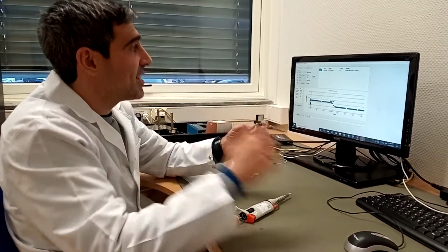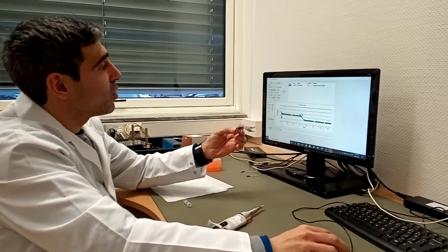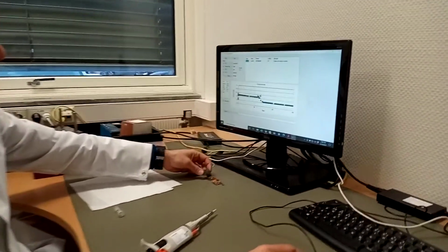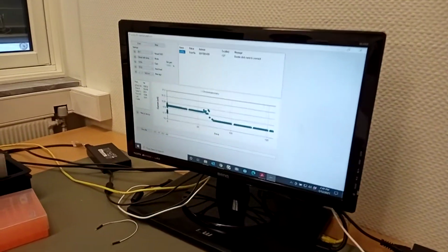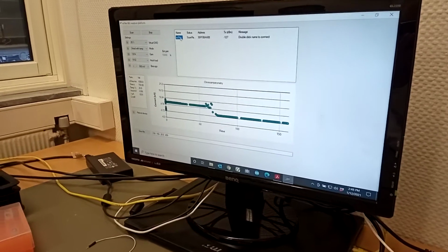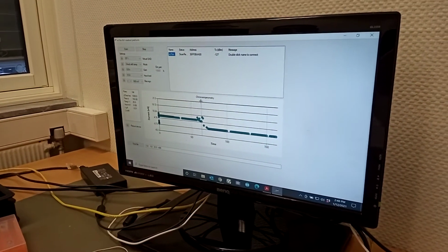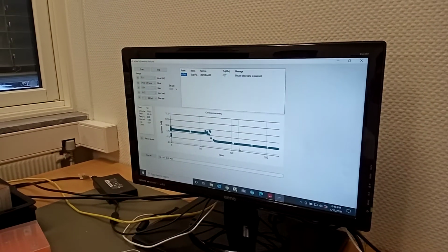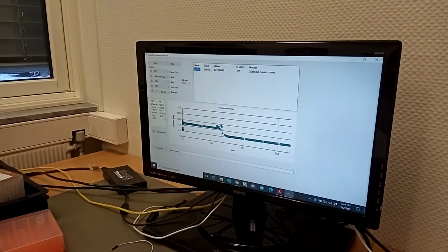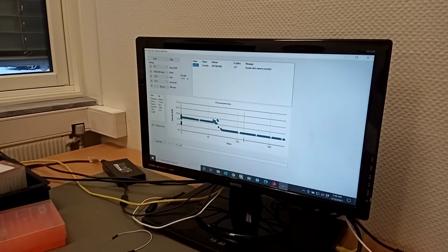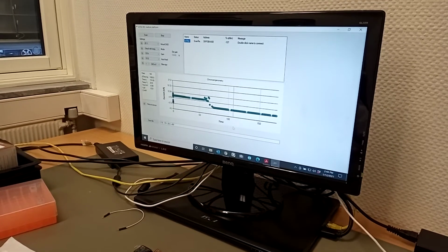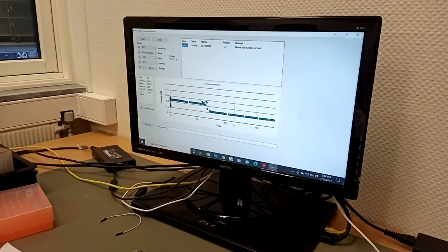So once this is done, you then need to use the software, the Bluetooth readout platform software developed by Zimmer & Peacock. In this case, we'll need to scan for your device and then double click on the device's name in order to connect. This is a chronoamperometry that we are demonstrating here. At this moment, the cell is dry, so it's showing 0 microamps. It's showing the current versus time, which is basically the same process as for the glucose sensor.